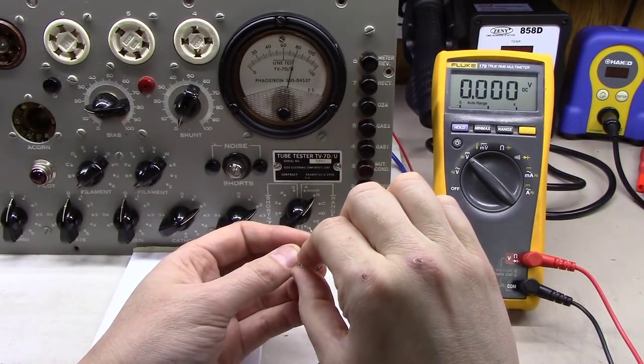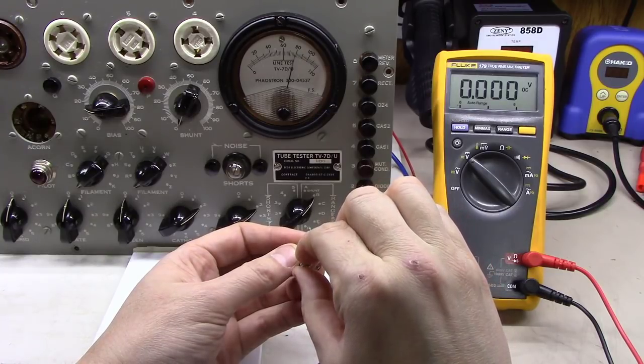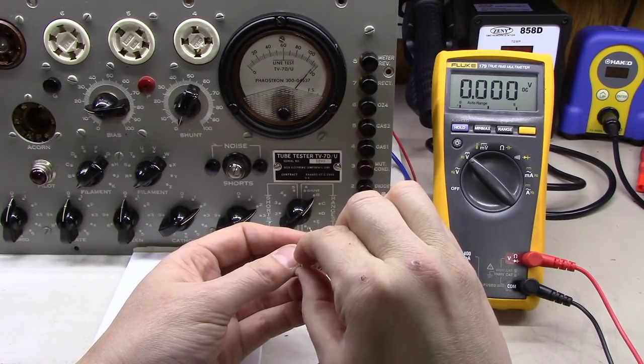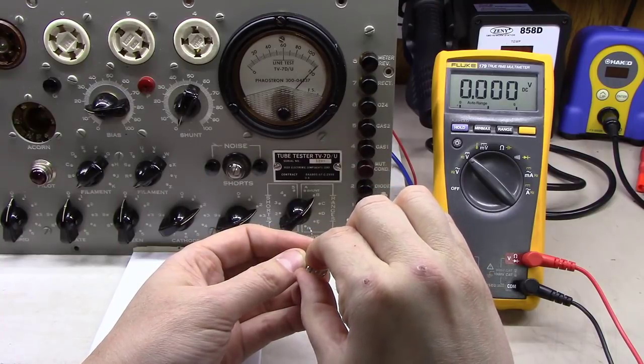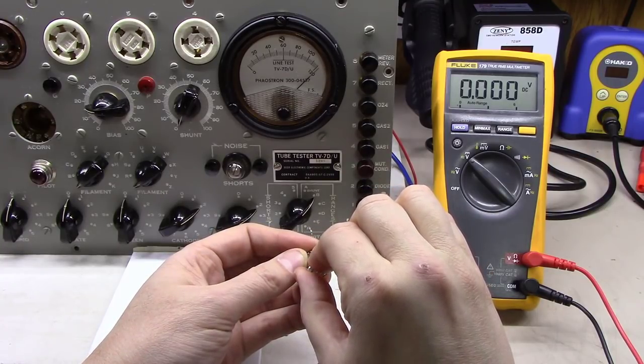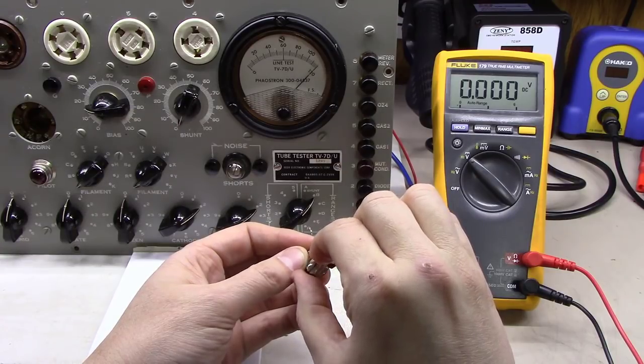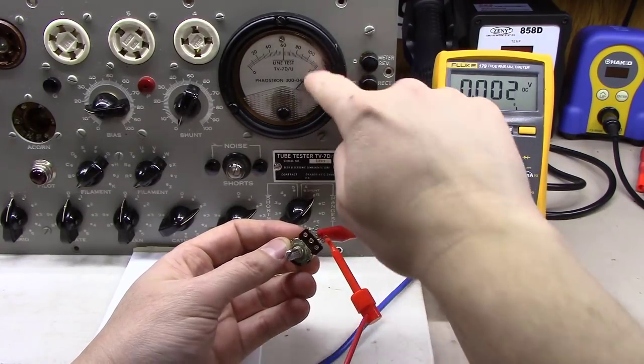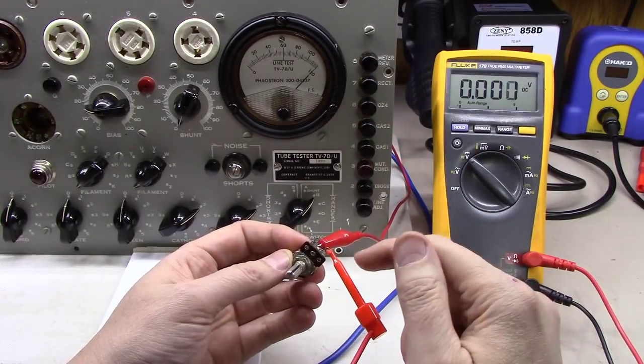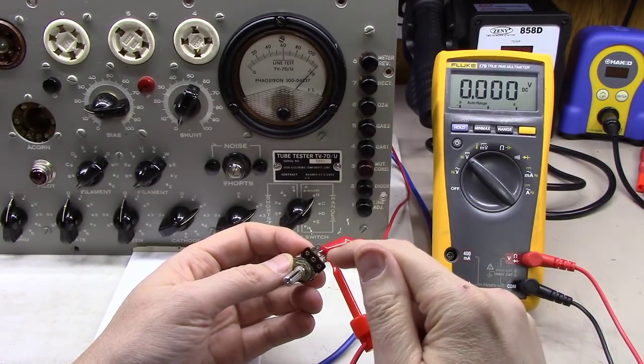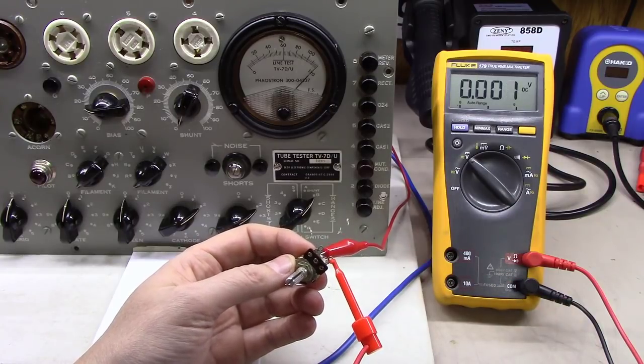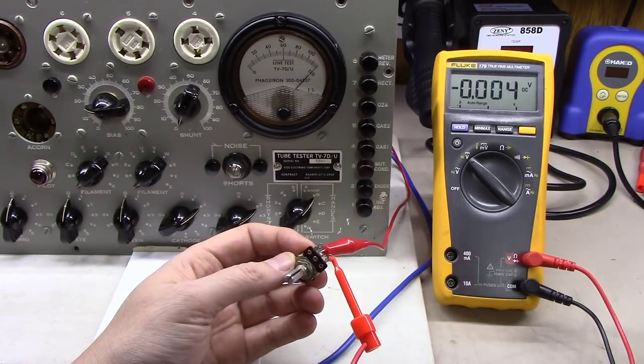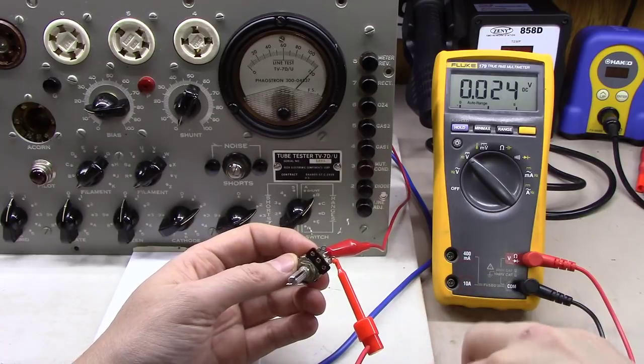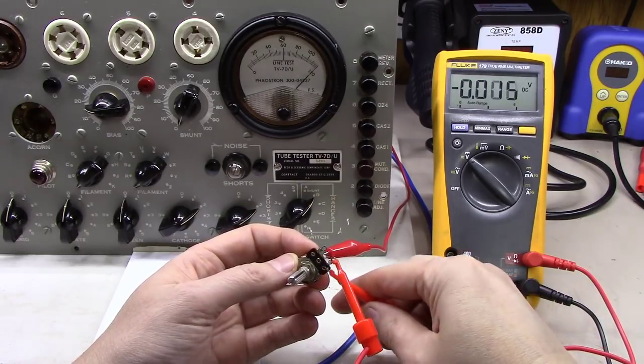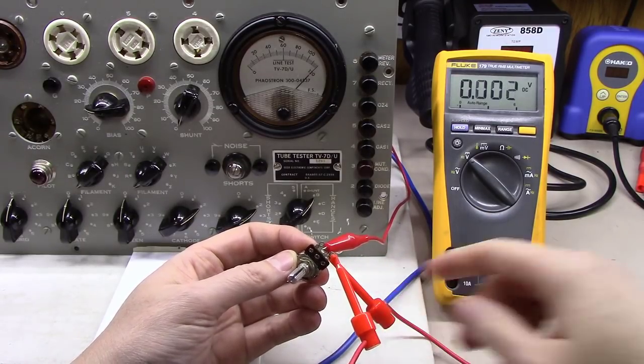And then what you're going to do is just adjust this potentiometer ever so slightly until you get that thing set. Whoops, thing's touchy. Very, very touchy. Right there, full scale on the 120 mark. And then at that point, you're going to want to measure the voltage across these 2 points right here. We can do that just by having the meter here hooked to voltage and come over here and connect onto one side of this little thing.